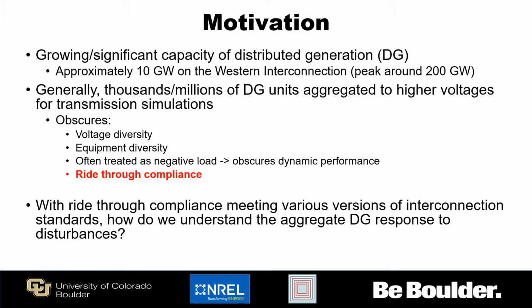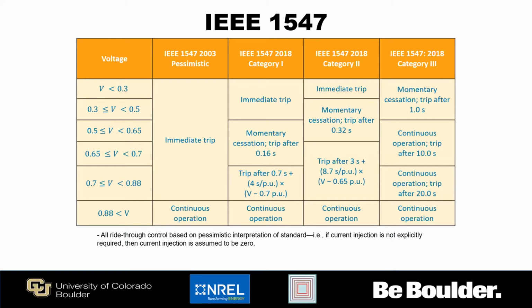So ride-through is a very important aspect of distributed generation. And so we want to look at different levels of ride-through compliance and how that will impact the aggregated DG response for disturbances. The IEEE standard which governs this ride-through performance is IEEE 1547. The original case in 2003, we'll call the pessimistic case. Here, the original intent was there were very small amounts of distributed generation on the system, and so they were encouraged to get offline very quickly whenever there was an issue, and this was primarily for lineman safety.